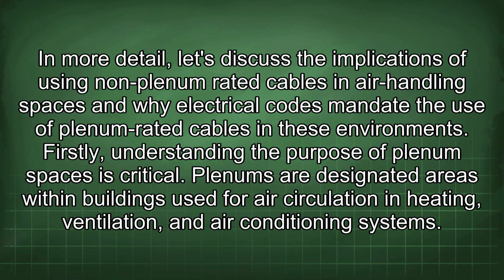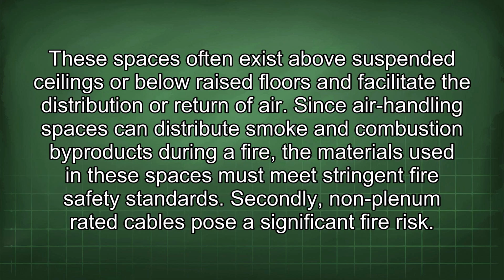In more detail, let's discuss the implications of using non-plenum rated cables in air handling spaces and why electrical codes mandate the use of plenum rated cables in these environments. Firstly, understanding the purpose of plenum spaces is critical. Plenums are designated areas within buildings used for air circulation in heating, ventilation, and air conditioning systems. These spaces often exist above suspended ceilings or below raised floors and facilitate the distribution or return of air. Since air handling spaces can distribute smoke and combustion byproducts during a fire, the materials used in these spaces must meet stringent fire safety standards.